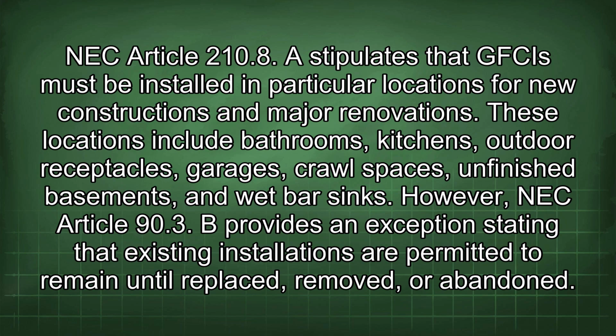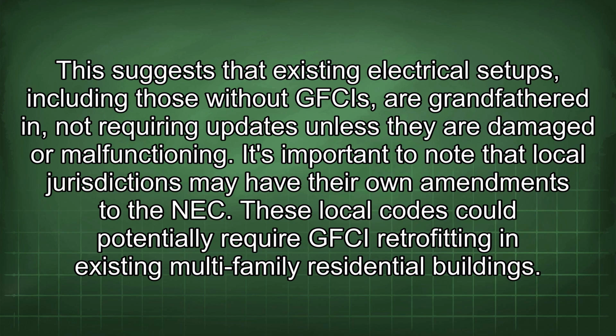These locations include bathrooms, kitchens, outdoor receptacles, garages, crawl spaces, unfinished basements, and wet bar sinks. However, NEC Article 90.3b provides an exception stating that existing installations are permitted to remain until replaced, removed, or abandoned. This suggests that existing electrical setups, including those without GFCIs, are grandfathered in, not requiring updates unless they are damaged or malfunctioning. It's important to note that local jurisdictions may have their own amendments to the NEC.